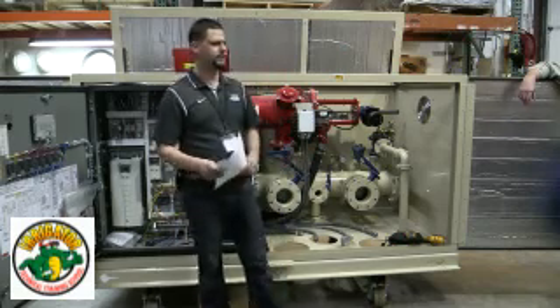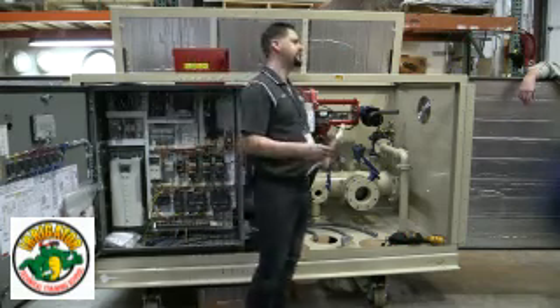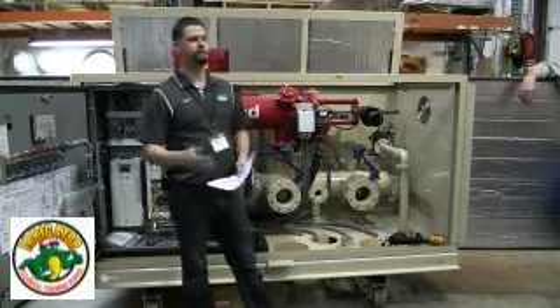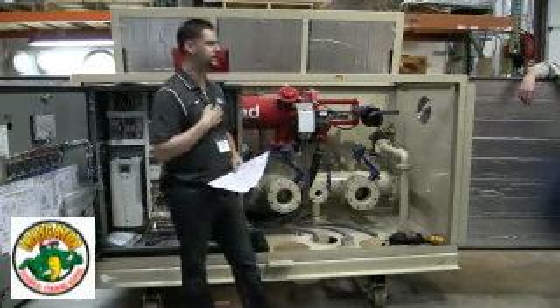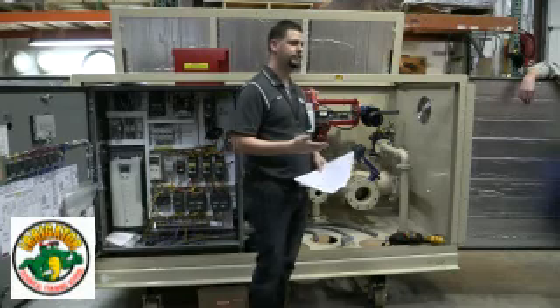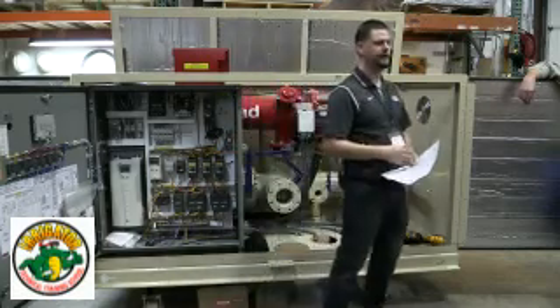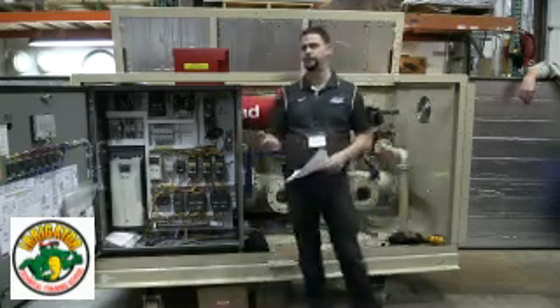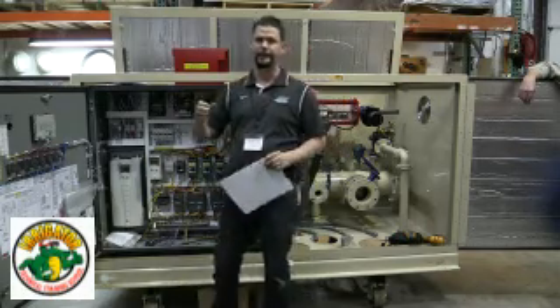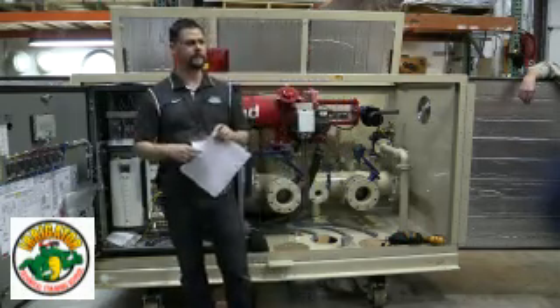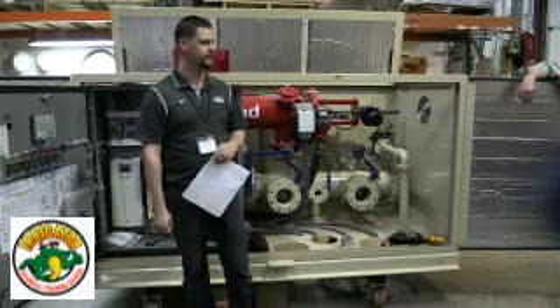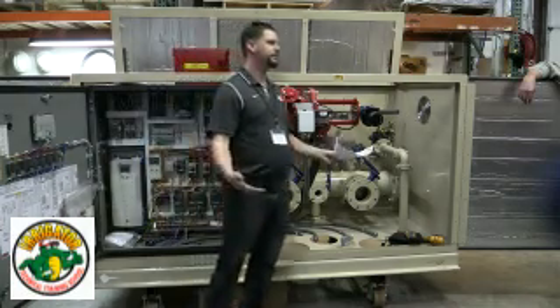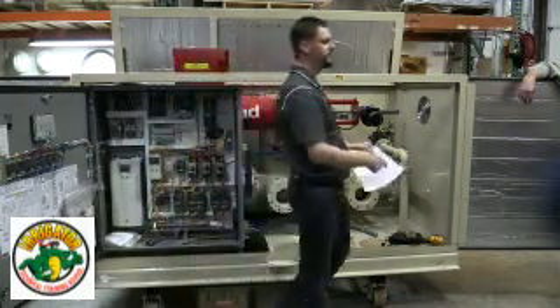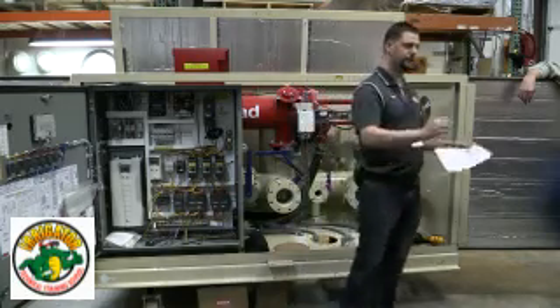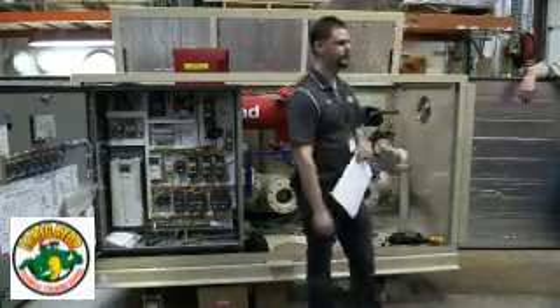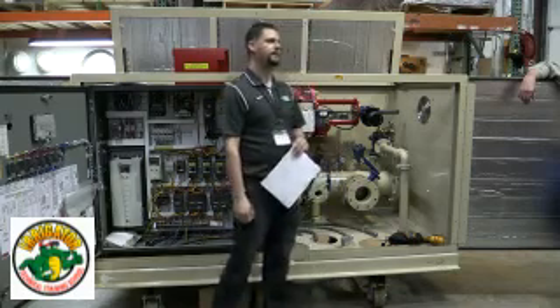Now the high pressure switch or low pressure switch—personally, I've never had freeze damage to a switch. However, I have pulled off a bunch of high pressure switches and low pressure switches where the bottom port is totally clogged up with rust and who knows what else. So I always make it a point to include that in the winterization as if it were a transducer, mostly to look at that port, and if it's clogged up with whatever, usually rust, I can clear it.